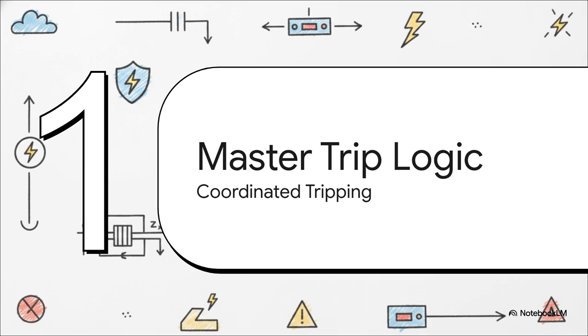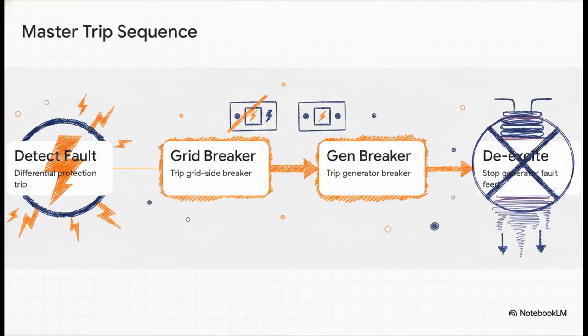Which leads us to the final piece of the puzzle. Section 5, Coordinated Master Trip Logic. You see, all of those advanced protection stages have to converge into a coordinated master trip. Look at these 4 mandatory steps. 1. Detect the fault. 2. Trip the grid breaker. 3. Trip the generator breaker. And 4. Initiate field de-excitation. If your differential protection detects a fault in record time, but your master trip logic only sends a signal to the grid breaker, you have completely failed to protect the transformer. You absolutely must hit all these breakers and the excitation system to fully isolate the fault from both independent sources.